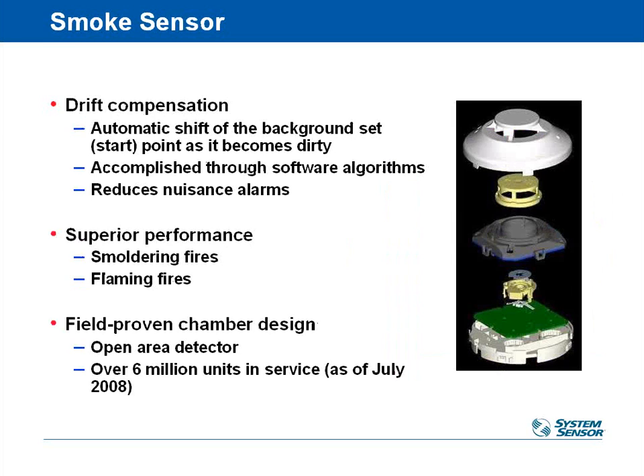These detectors have a built-in drift compensation, which means they're basically always calibrating themselves to a baseline through a software algorithm in the detector itself. So it works kind of like some of the CO2 sensors we've used over the years, where they figure out what their baseline value is and then constantly recalibrate themselves to that, which prevents small nuisance trips over time. So it's only going to alarm if there's a substantial amount of smoke and not a little bit of drift or something due to dirt or something of that nature.